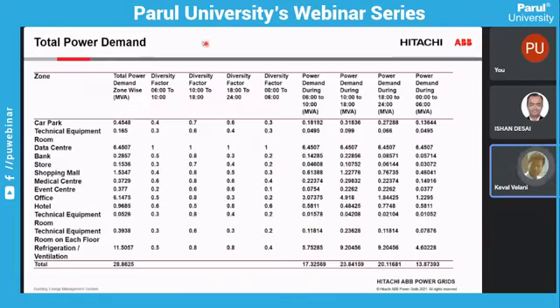Here you can see the total power demand for a particular building. These are the particular building premises: car parking area, technical equipment room, data centers, bank, storeroom and shopping area. Store means particular normal stores, mostly available in first and second floors in public utility buildings. Then shopping malls, medical center, event center, office, hotel, technical equipment room, technical equipment, refrigeration and ventilation. Here you can see the total power demand zone wise. This is the diversity factor.